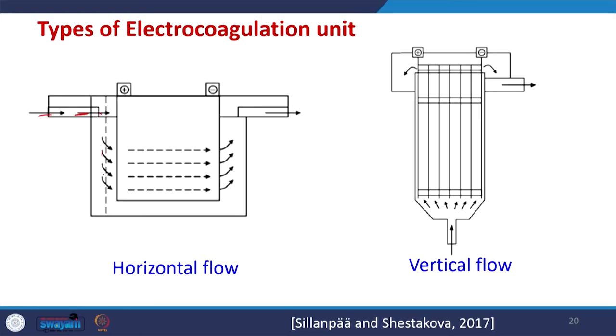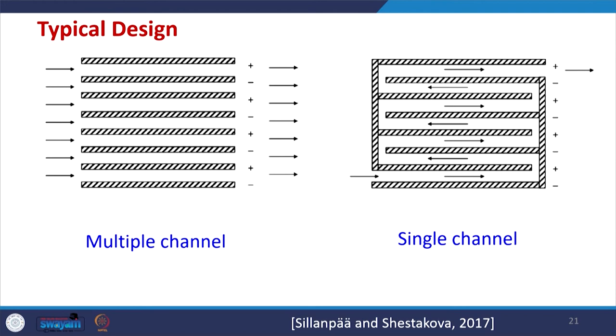Different types of electrocoagulation units are shown here. We have different configurations: vertical flow and horizontal flow. The electrodes are connected in either monopolar or bipolar mode, with water going up and after treatment settling down, with sludge settling at the bottom. The typical design has a positive and a negative terminal with water flowing through. There is a multichannel possibility and a single-channel possibility where water enters and treatment occurs as it passes through. These design units apply to electrooxidation as well.